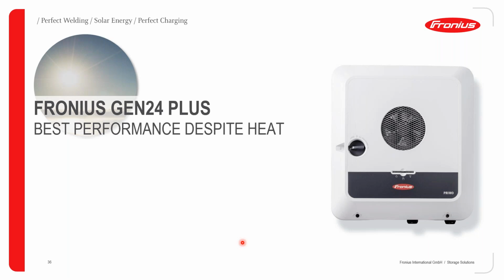Another important consideration of the Gen 24 inverters is that these inverters, just like the other Fronius Snap inverter series, are actively cooled. So you get the best performance despite heat through this active cooling technology. The biggest difference that you can note here is that we have a cooling fan positioned at the front of the inverter. You can see it from the front cover of the inverter. With a normal Snap inverter series, the cooling fans are normally on the sides of the inverter. So this is a very unique design with the Gen 24, because now this entire face where the cooling fan is located is the heatsink, and the dissipation of heat happens all around the inverter through the provided slots.